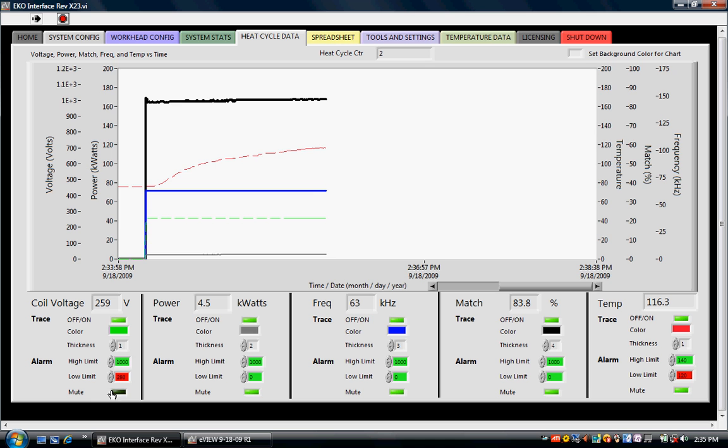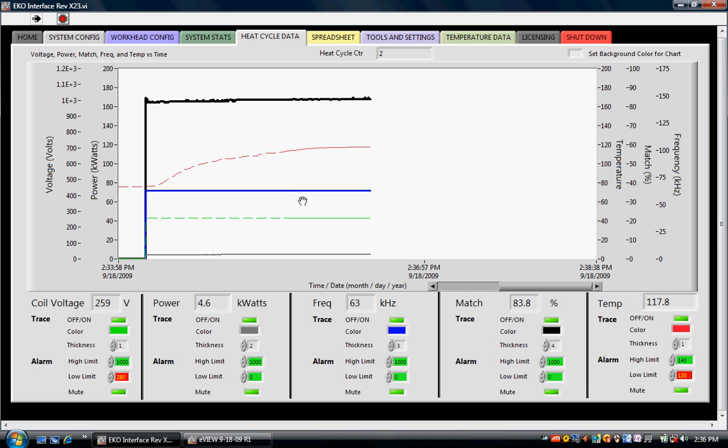The EKOHeat has one analog input channel. If the power supply is not operating in a closed-loop control mode, this input is available to monitor temperature. To monitor temperature, the user connects an analog signal, preferably a 4 to 20 milliamp signal, to the analog input. This signal is sent to eView and displayed on the graph. It's also stored in the spreadsheet. eView allows the operator to enter calibration information for the signal. Temperature monitoring is a key aspect of induction heating. Temperature measurements can be used to validate a new application or monitor an established process.